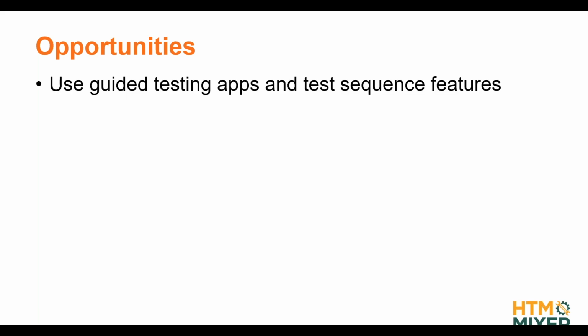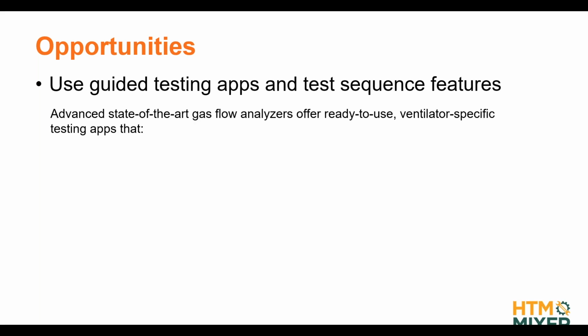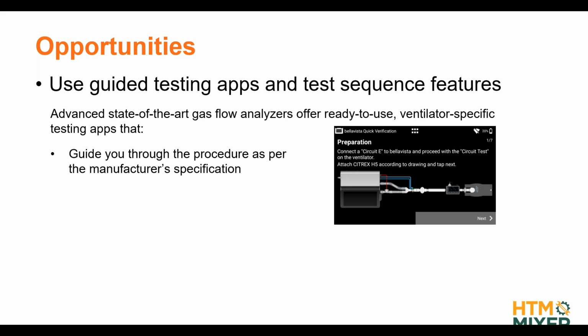The last opportunity that I want to present you here is something that not many gas flow analyzers have, but this is actually what our gas flow analyzers, for example, the latest ones have. And it's to use guided test sequences. We call them testing apps. So what these testing apps do is they guide you through the performance verification of the ventilator step by step by kind of mirroring the user manual in a guided procedure on the screen.